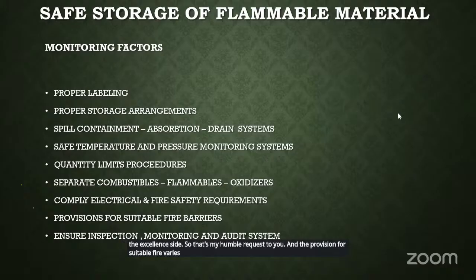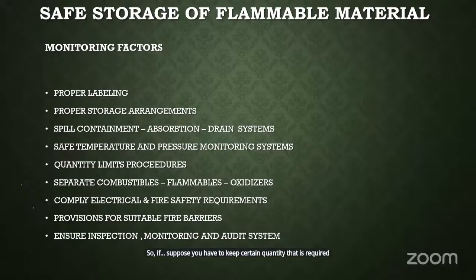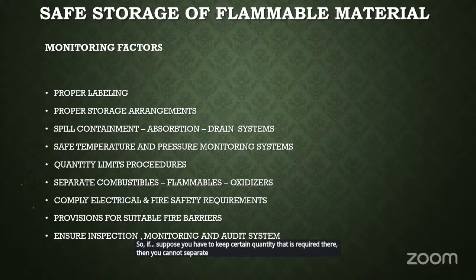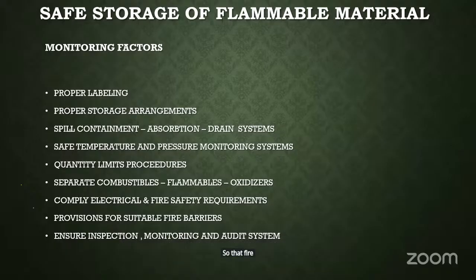If you have to keep a certain quantity that is required there, and you cannot separate the flammable from the oxidizer or something like that, then try to provide a suitable barrier system, if applicable, so that unnecessary fire can be prevented.